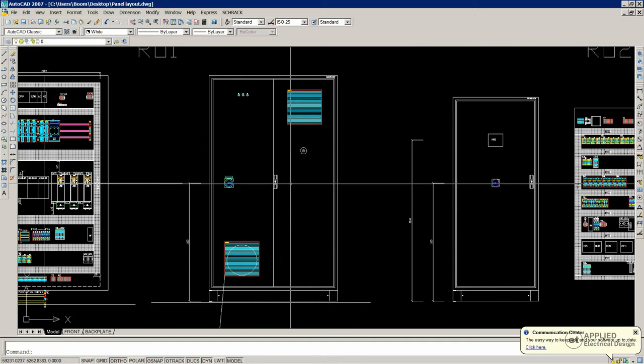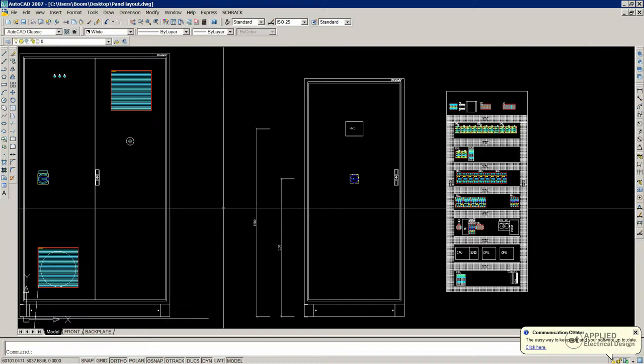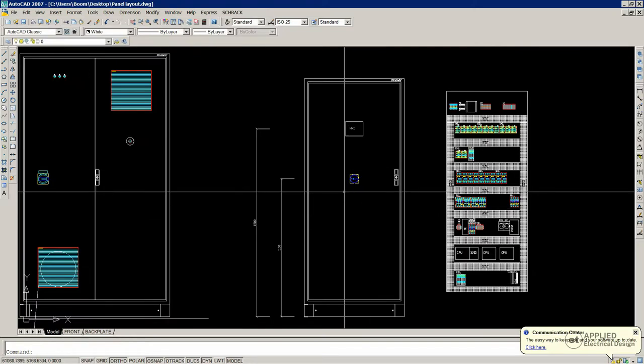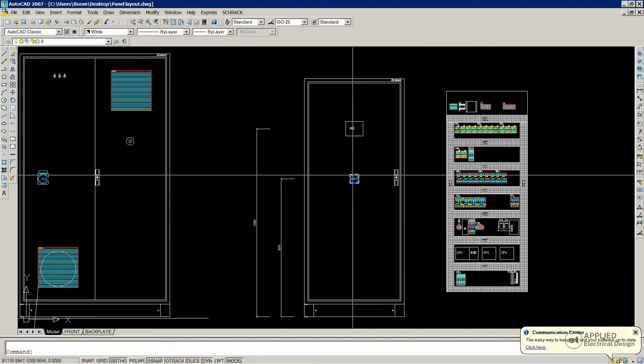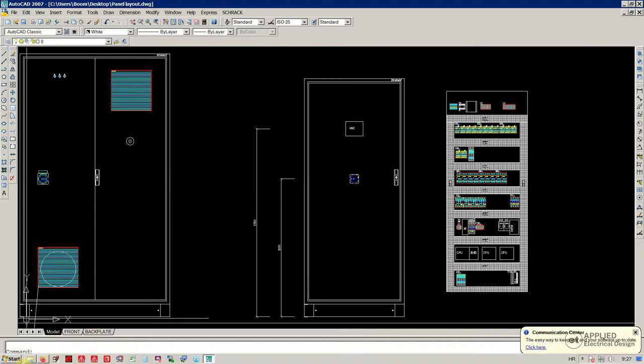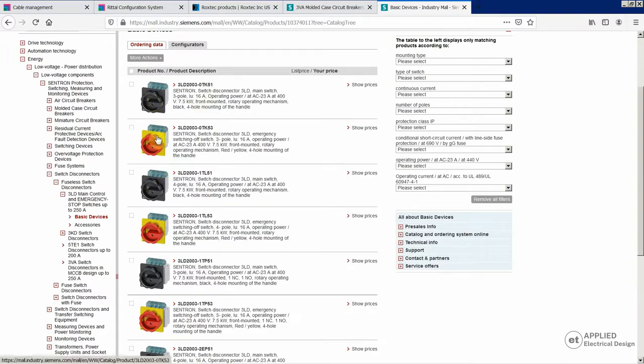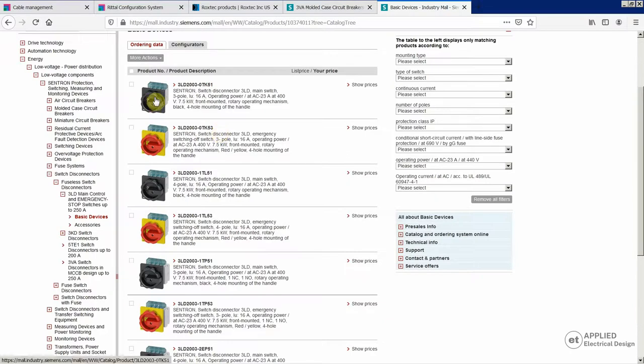First of all, you would probably have a main switch. You would have two basic versions - either the switch disconnector, like here, and this is an example from Siemens. Two basic versions - black or red and yellow. These do not have a protection possibility, they just disconnect your circuit, so your power supply.